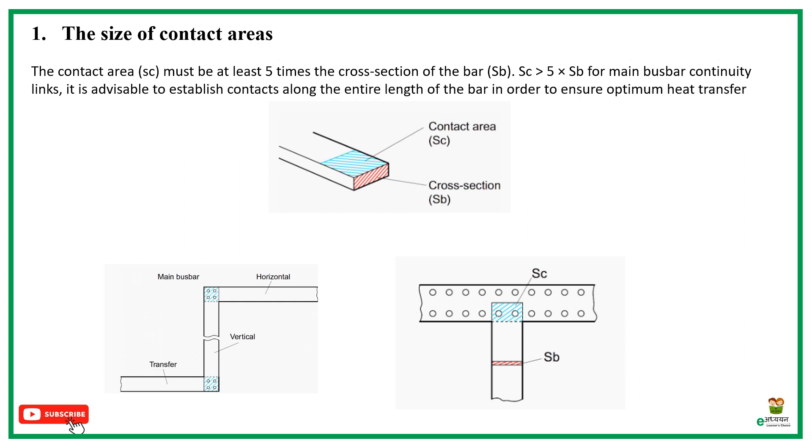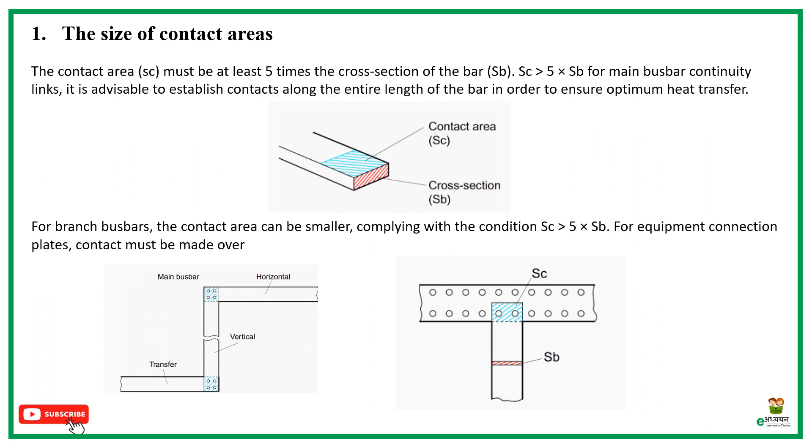It is advisable to establish contacts along the entire length of the bar in order to ensure optimum heat transfer. For branch busbars, the contact area can be smaller, complying with the condition SC is greater than 5 times SB. For equipment connection plates, contact must be made over the whole surface of the plate for use at nominal current.